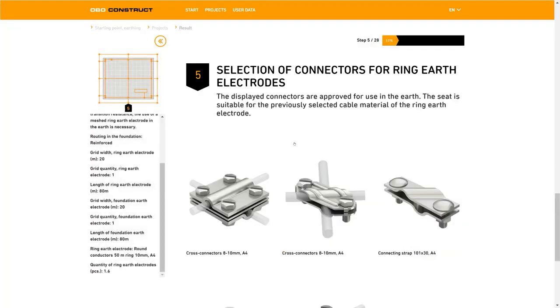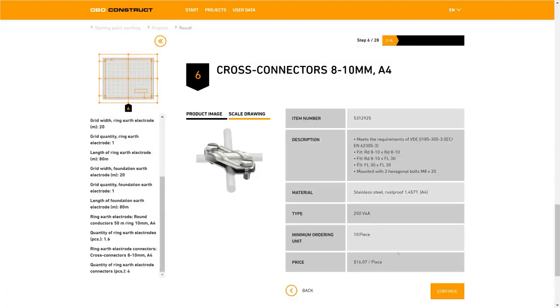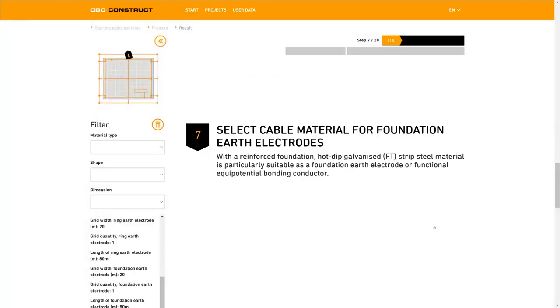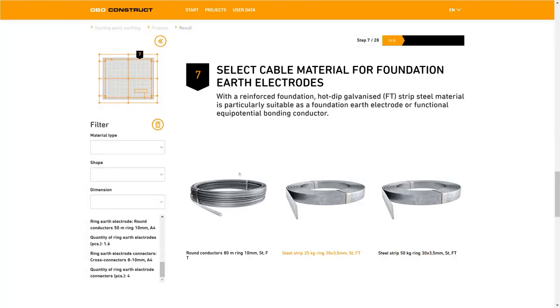Next we come to the selection of the connector for the ring earth electrode, at which point we jump to step 5. As you can see step 5 is displayed here, and also at the top this bar shows you the stage at which you are at the moment. In our case we're at step 5 of a possible 28, which equates to approximately 17%. By choosing the cross connector in A4 we come to the next step. The foundation earth electrode is covered with 5 centimeters of concrete, which means we can select normal hot dip galvanized products here. So we'll take the round earth conductor again.